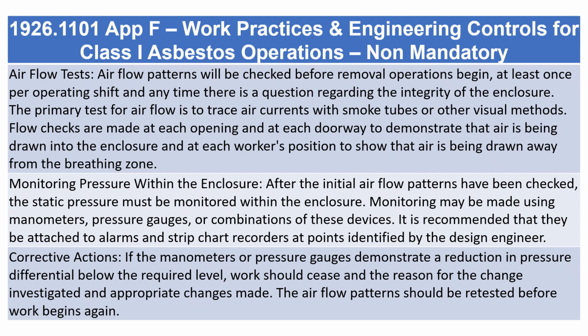Monitoring pressure within the enclosure. After the initial airflow patterns have been checked, the static pressure must be monitored within the enclosure. Monitoring may be made using manometers, pressure gauges, or combinations of these devices. It is recommended that they be attached to alarms and strip chart recorders at points identified by the design engineer.